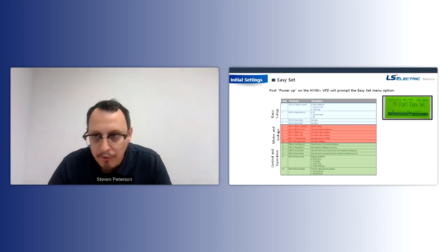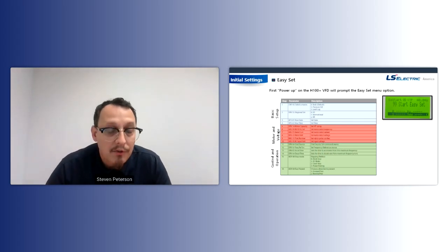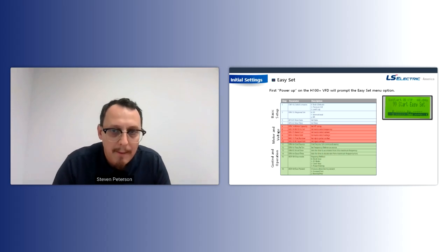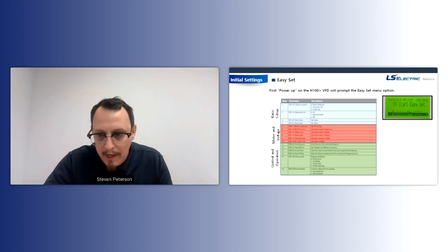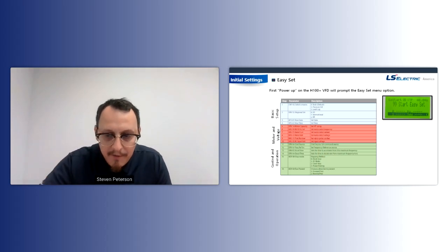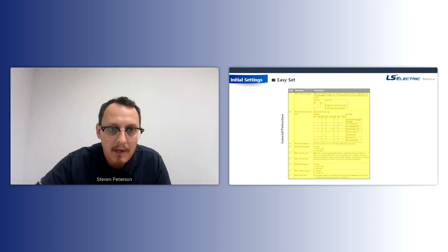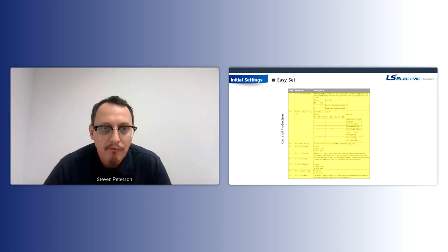A region, which is most likely going to be US. You set up your time, which we briefly mentioned. You set up your motor voltage and your incoming voltage and your motor current. And then you go on and set up your control and operation. Okay. And you pretty much just linearly go down this list, and it's going to end with all these general protection features. I have some slides that come up on pretty much each one of these, so we're going to explain why you set these and what they do.